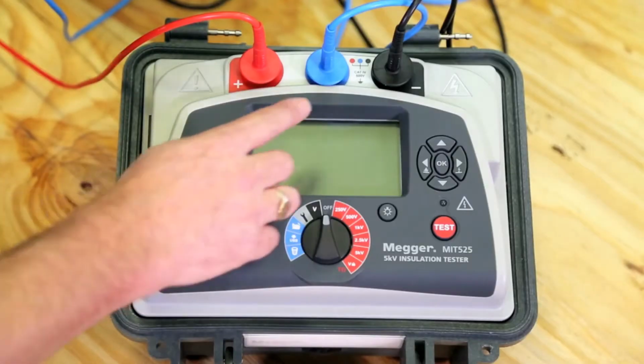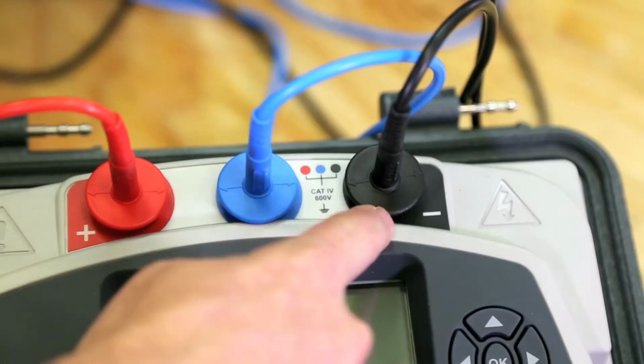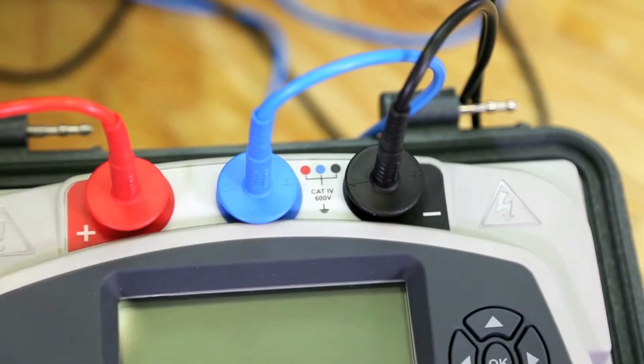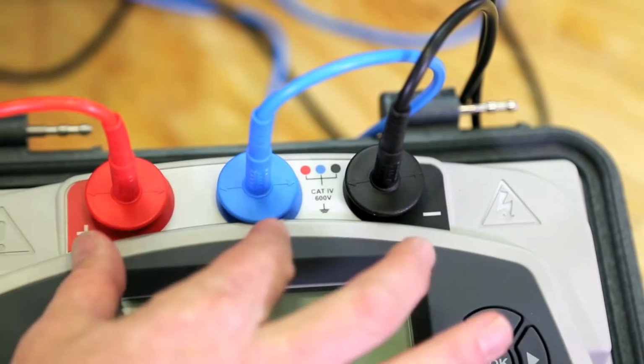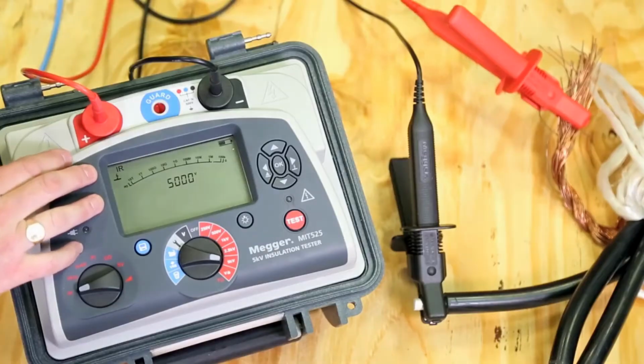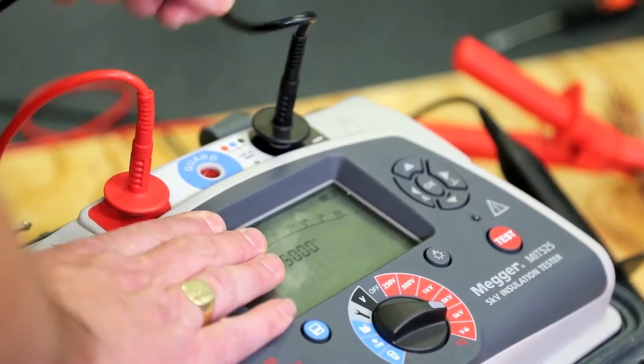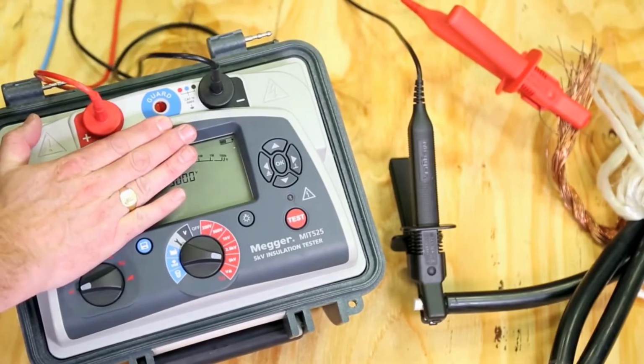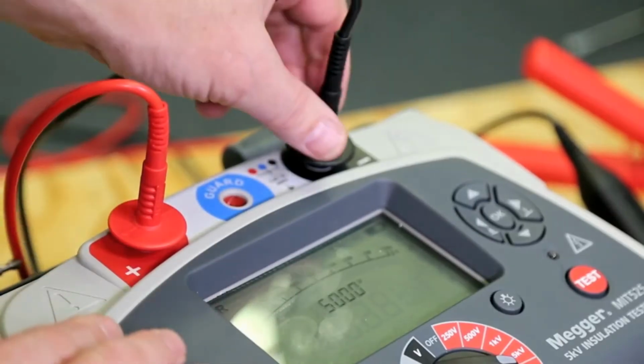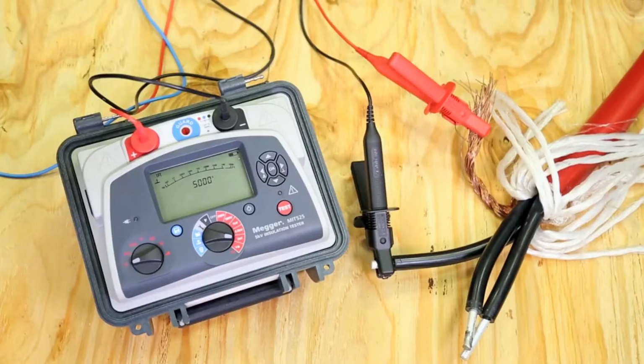All three terminals are rated to category 4, 600 volts, and 1000 volts between each of them, protecting the unit against misconnection. The lead terminations lock to prevent accidental disconnection. Capacitive loads must be safely discharged after testing. MITs do this automatically. If the test leads disconnect, it could be extremely hazardous.